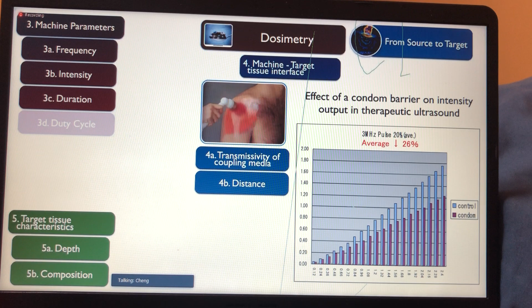So that's something you need to think about when you're putting something between the transducer and the tissue interface. If you're just using gel, you're fine. But anything that comes in between, you really have to check that carefully. The next one is depth. So we went down as far as 5 cm. Beyond 5 cm, I wasn't going to go, because I don't think in clinical applications you have anything more than 5 cm. So we stuck with 5 cm.